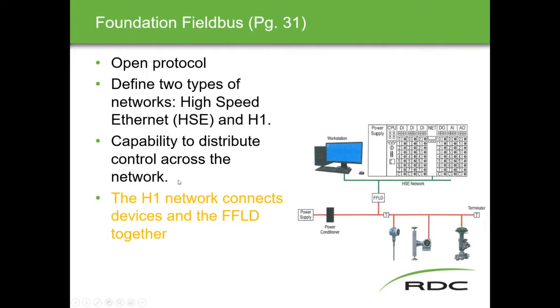Okay, what is unique about Foundation Fieldbus is the capability to distribute control across the network. And what that means is a Foundation Fieldbus device can have PID control built into the device. So it doesn't have to be part of your program, which is unique. I don't know the applications where you would do that, but that is what makes Foundation really unique compared to HART and DeviceNet, the fact that it can do PID stuff right inside the devices themselves. Okay, the H1 network connects devices and the FFLD together. That's not exactly true. The FFLD connects the H1 network to the HSE network.